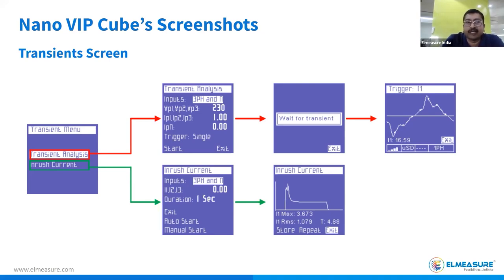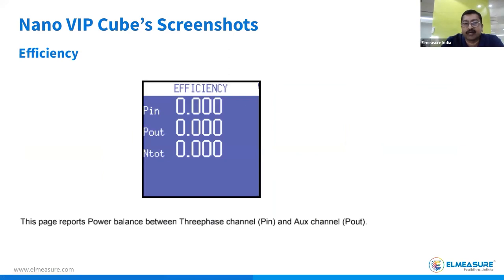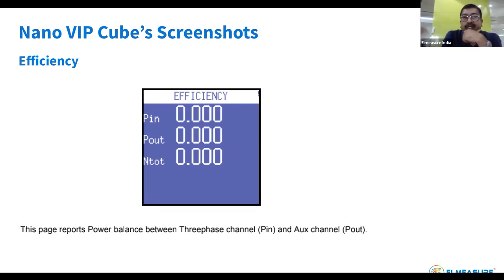They can see the inrush current, you can see the map provided. One important feature is you can look at inverter efficiency also, where you connect the input at the raw AC current, and on the secondary side you connect the DC current, using the options provided, and you straight away get the efficiency in the meter itself—no need to do any mathematical calculation. You can have the data built upon that.